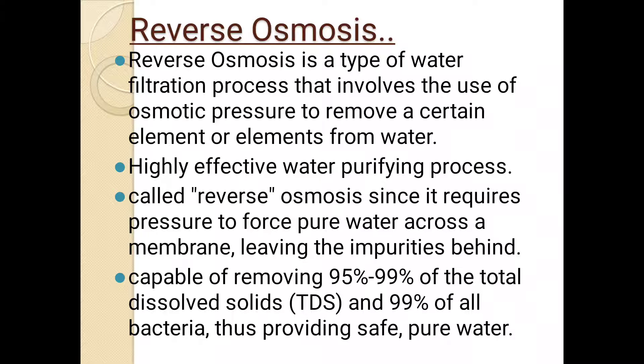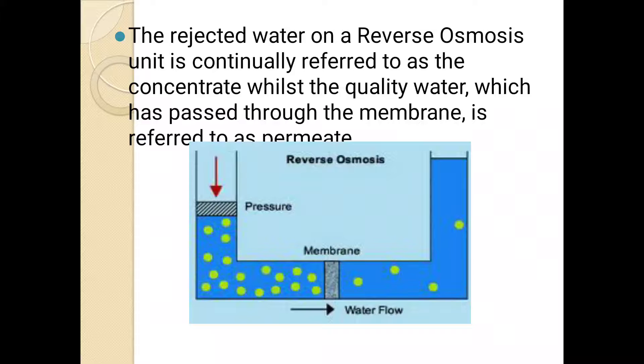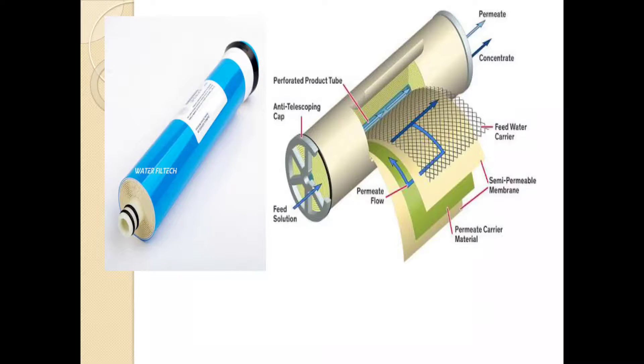Reverse osmosis is recommended for the water purification process. The rejected water on the reverse osmosis unit is referred to as the concentrate, while the quality water that has passed through the membrane is referred to as the permeate. The membrane module consists of components including the permeate carrier material, semi-permeable membrane, feed water carrier, and anti-telescoping cap.